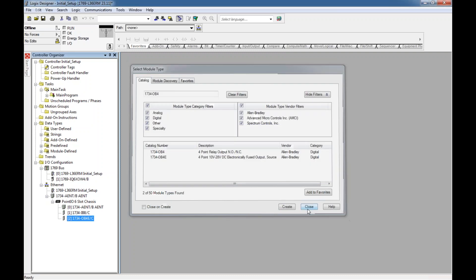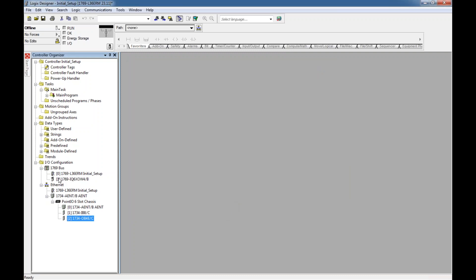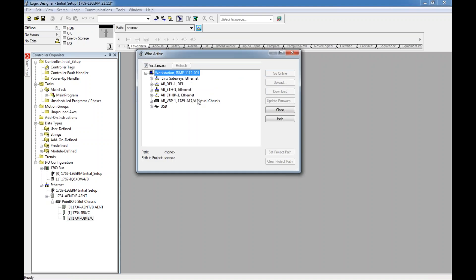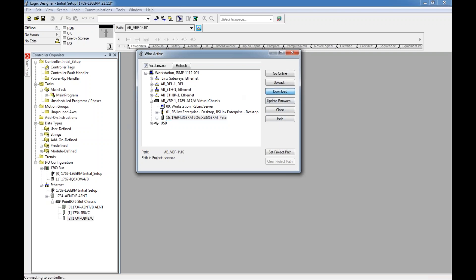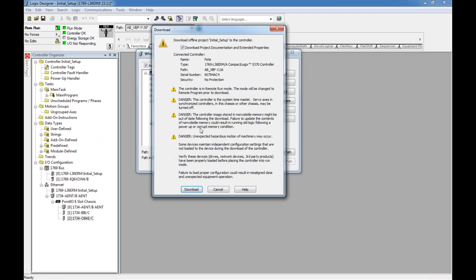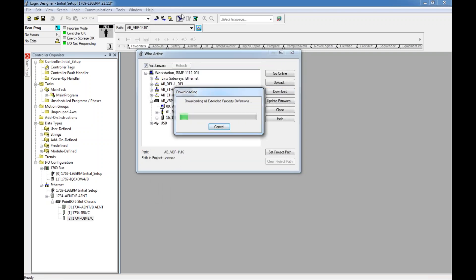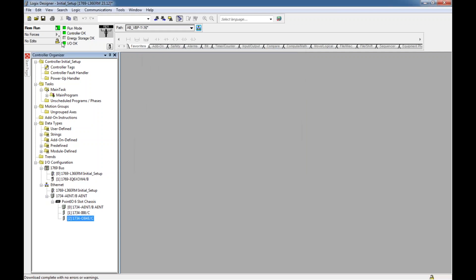I close the module browser. Now I have my input card on the local bus and my input/output cards on the Ethernet. I can establish my communication pathway — either by virtual backplane or USB; I usually use virtual backplane. I highlight the processor, download the new hardware configuration, set up the communication path by clicking 'Who's Active' in RS Linx, select Remote Run, and hit OK. You'll notice right here it should read 'IO OK'.